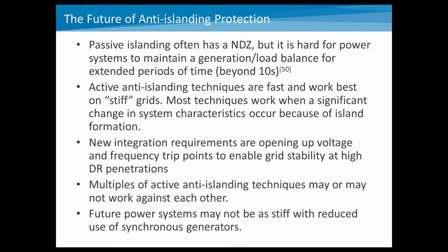So let's move on here. We're getting close to the end, and I'll talk a little about the future of anti-islanding protection. Here are some generalized conclusions based on the presentation. Passive anti-islanding techniques often have a non-detect zone, where they have some level of stable voltage and frequency that stays inside a normal area, and it's hard to detect inside that specific space. But it's also hard for power systems to maintain that generation-load balance for extended periods of time, depending on the control strategies of the distributed generation.